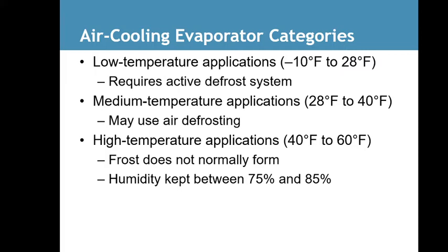Medium temperature applications, 28 to 40. Now that could freeze, but normally these are used down to 28 degrees for a beer cooler, something with alcohol in it. May use air defrosting. High temperature applications, 40 degrees to 60 degrees.